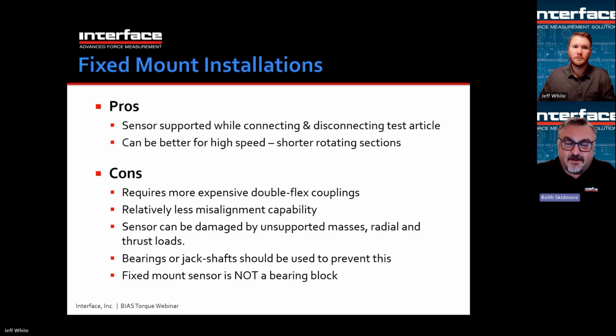So a lot of times you might have an extra bearing that goes into the test setup, and that test setup maybe takes overhung moment. So if you're going to have a torque sensor that has bearings, you don't want to use those bearings to support any radial load, but maybe there's some radial load that needs to be supported. For example, if you have a fan and you're trying to test a fan blade, you could potentially mount your fan straight to the torque sensor shaft and then see how much torque it takes to spin that fan. Well, the weight of the fan is going to create an overhung moment or bending on the shaft, and that may be damaging. And so what we would recommend is a coupling between the fan and the torque sensor and some kind of intermediate bearing to support the weight of the fan. Again, do not use the torque sensor as a bearing block. Bad idea. We don't want you to ruin torque sensors. Moving on.